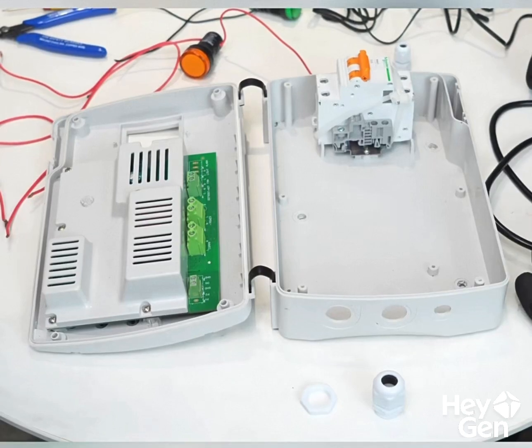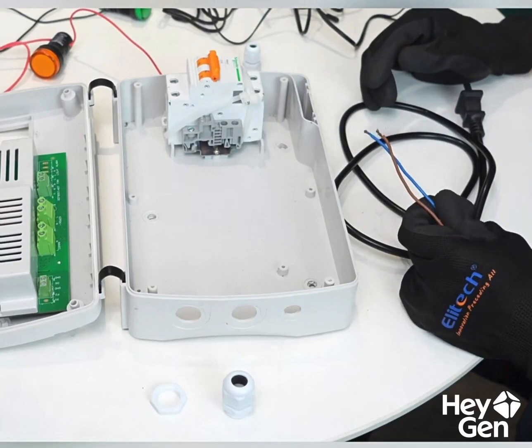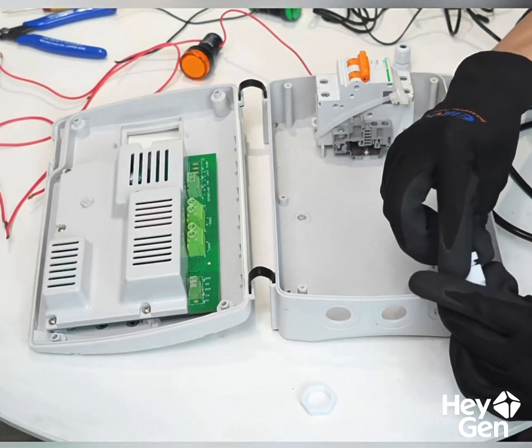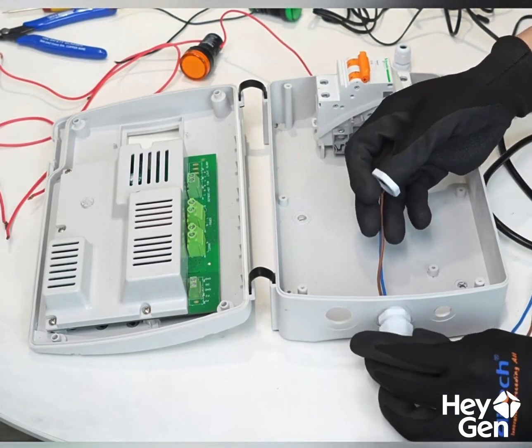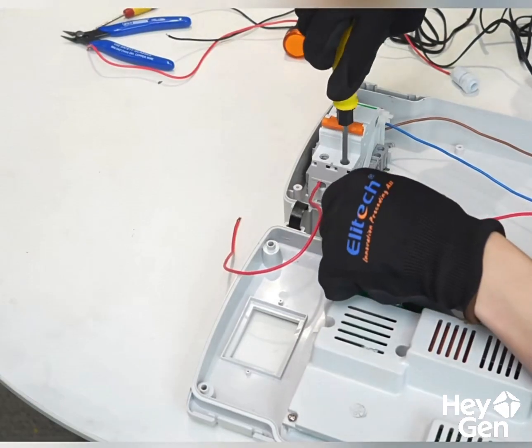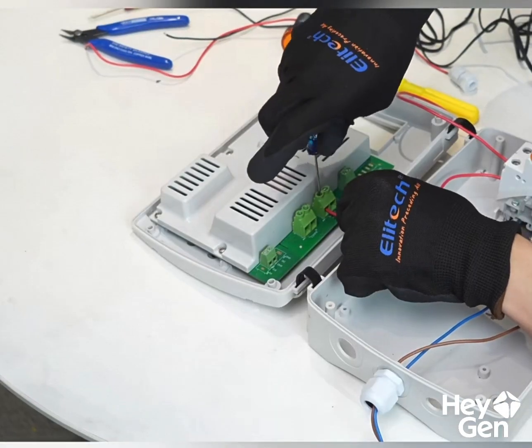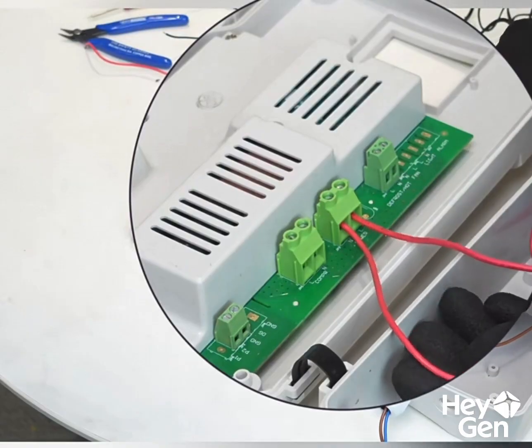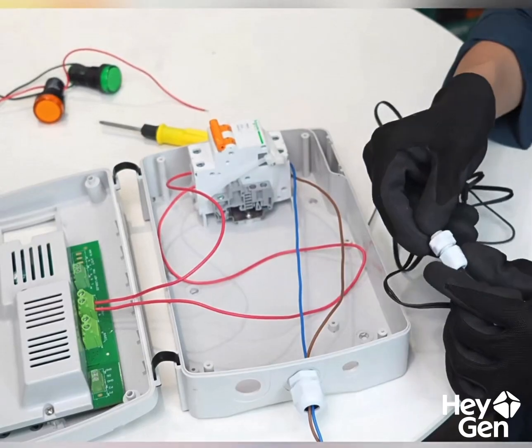Let me explain in advance the wiring method for the ECB1 GNP electrical control box. First, we prepare a power cable. Feed the two flexible wires of the power cable through the waterproof connector into the input terminal of the circuit breaker. Then, connect the output terminal of the circuit breaker to the input terminal of the power supply end in the control box, which are terminals number 5 and 6, the hard plastic ones.